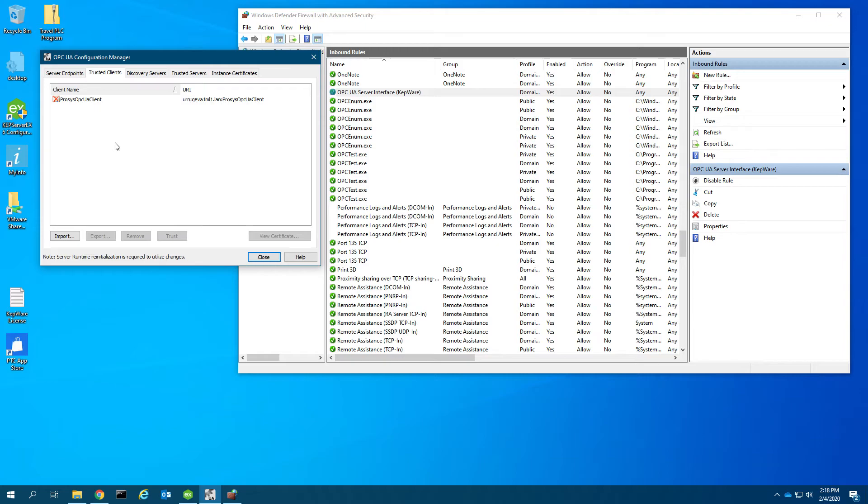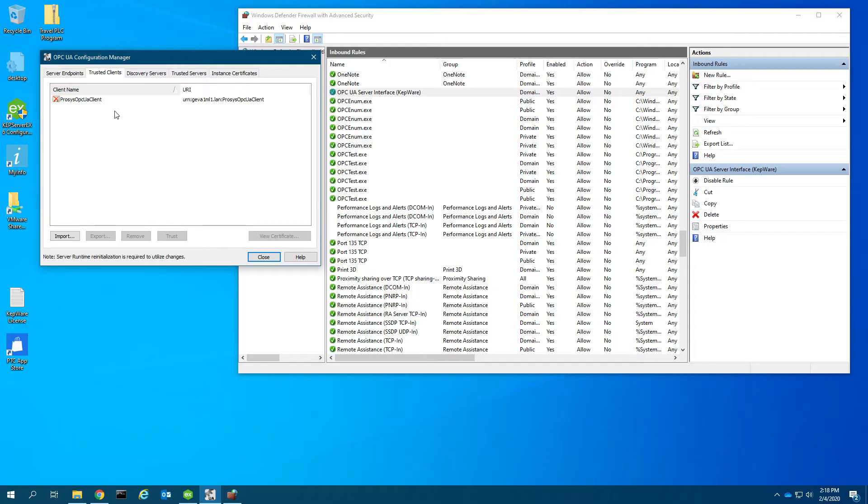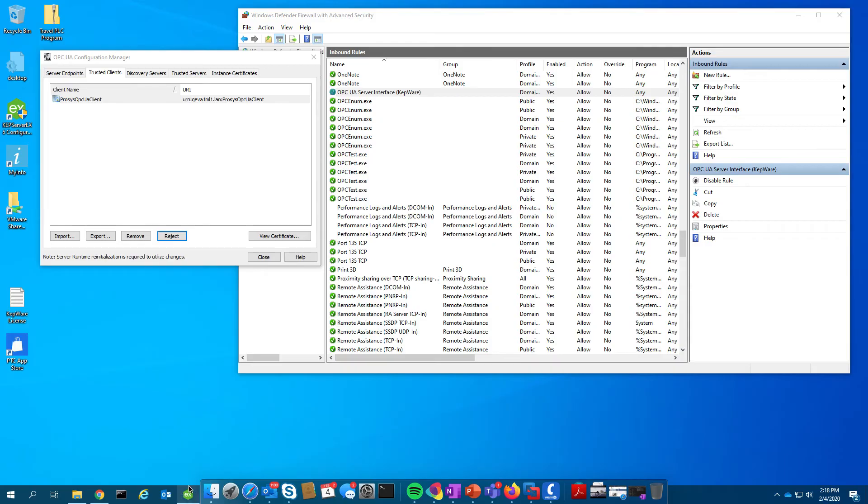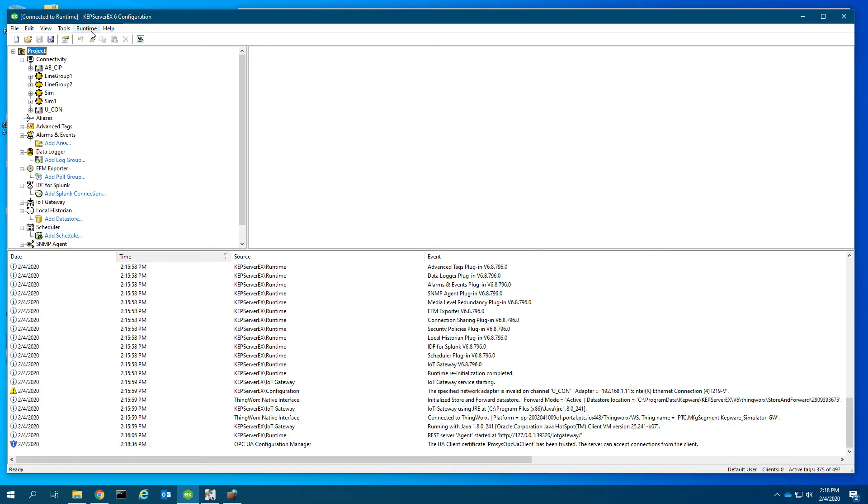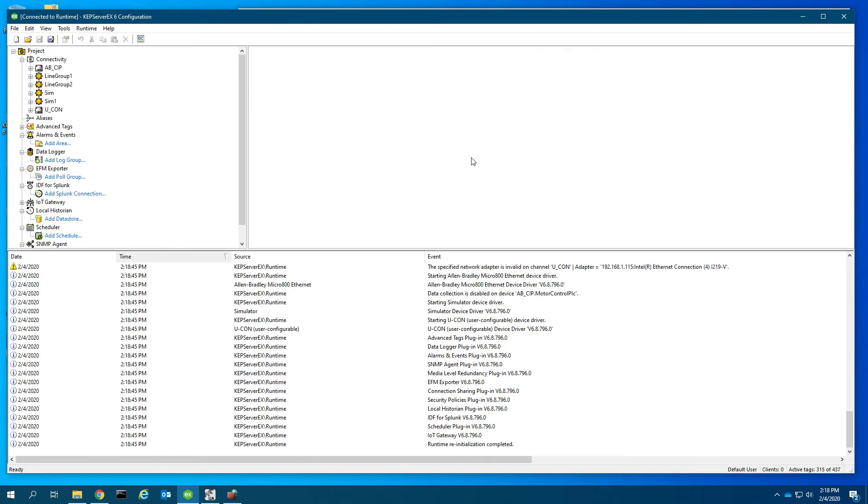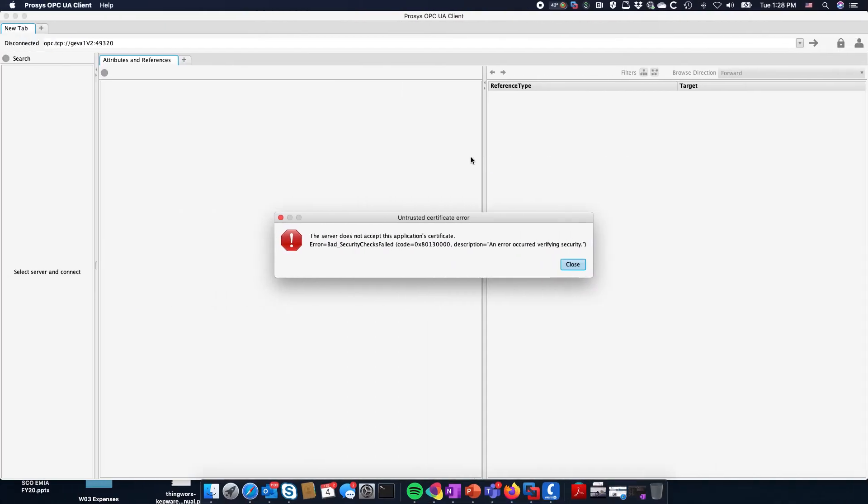Let's go back to the trusted clients tab. We'll see there's been a received certificate, a certificate exchange between the client which I have open, which is a Prosys OPC UA client running on Mac. This is a cross-platform OPC UA client that runs on Linux as well as Mac. I need to trust this particular certificate that was received.